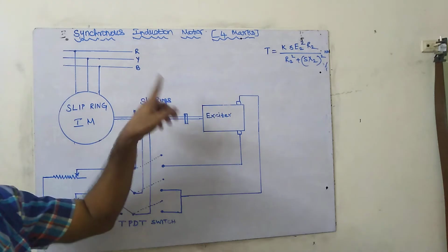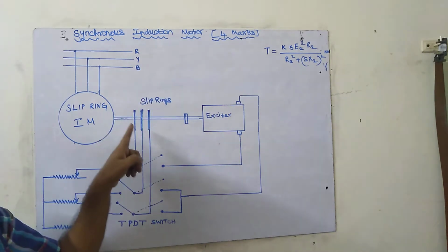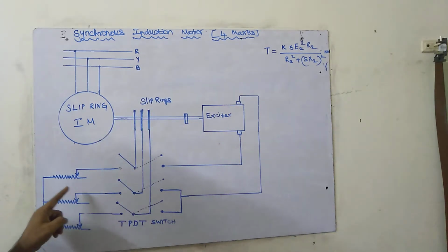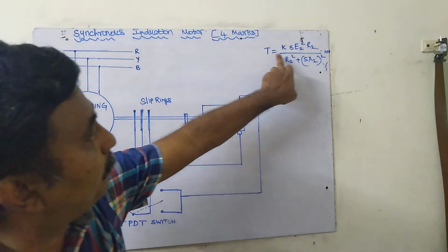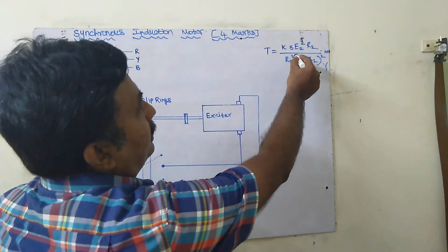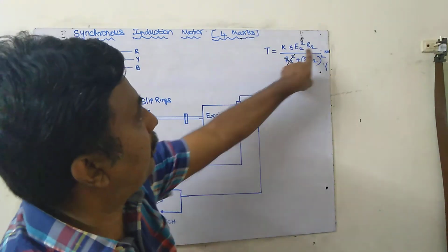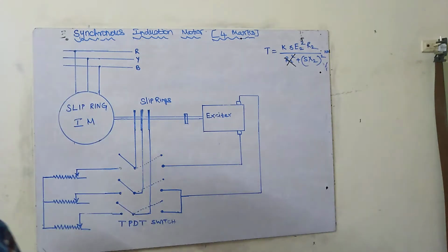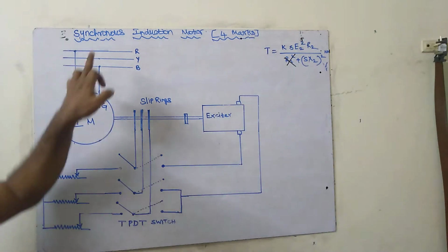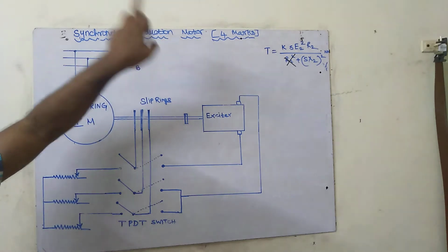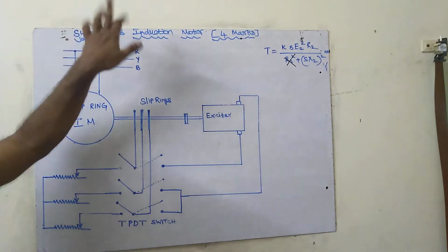So there also we are using which type of induction motor? Slip ring induction motor. By having slip rings, we are adding some extra resistance. What is the need for adding extra resistance? For increasing the starting torque. So we know that torque is proportional to R2, which comes into the picture at the time of starting. So starting torque is proportional to R2. That's the thing.